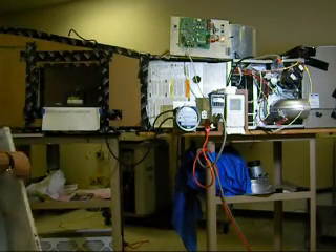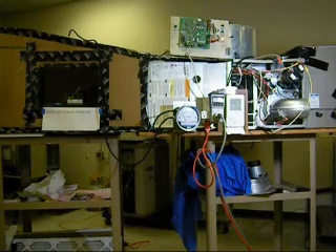39. We're starting at 4,000. This air is dirty. We're breathing it and we don't even see it. Yeah, because you've got all the traffic on the freeway and everything. Now watch it as the particle count comes down. 3,800. The static's not perfect this time — maybe it'll take a minute to settle out, or one of these things might have dropped again. So anyway, we're down to 37. It'll keep going down, and as all the air recirculates, the air gets cleaner and cleaner every 10 minutes. And it'll keep coming down.